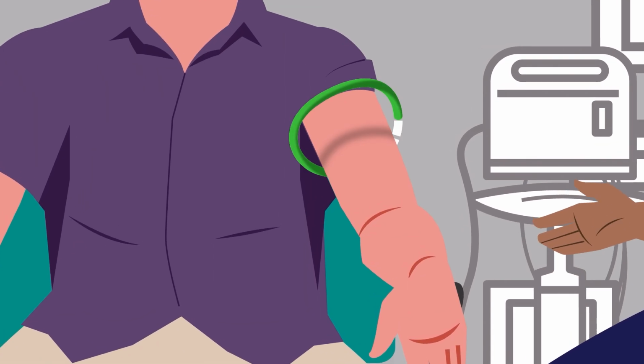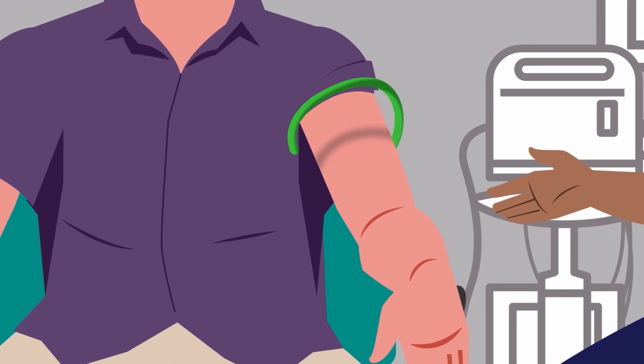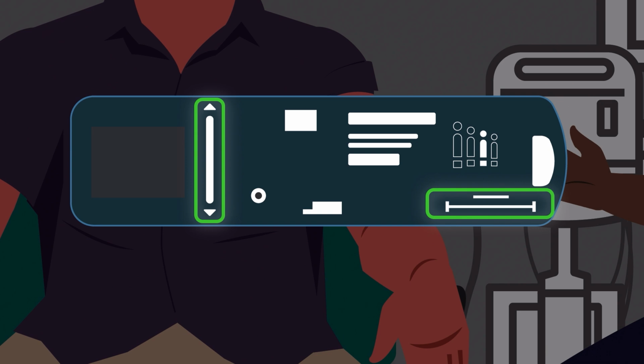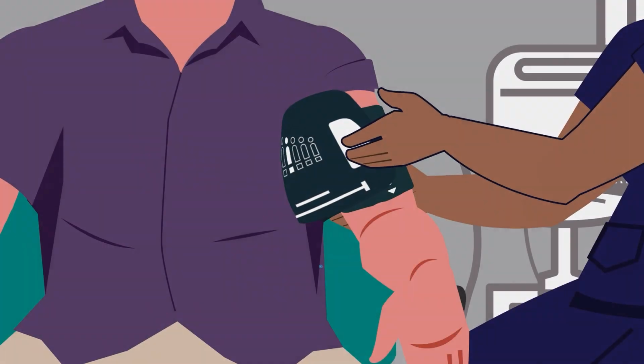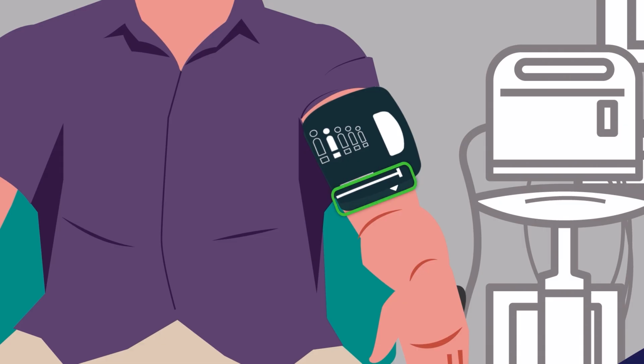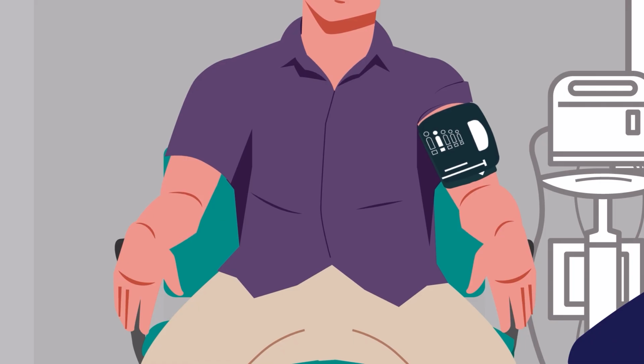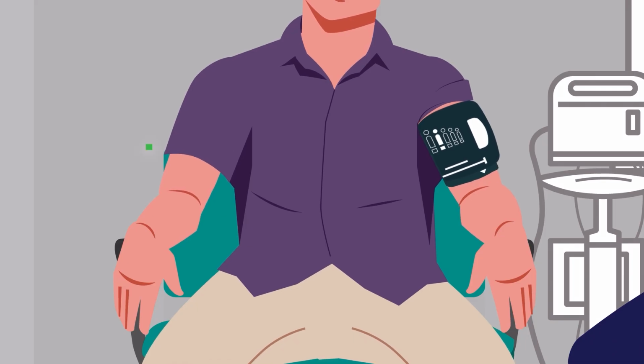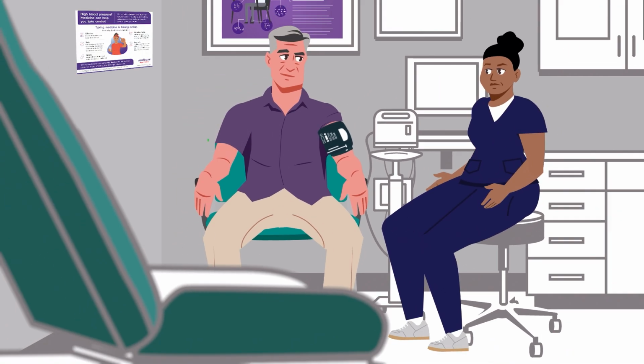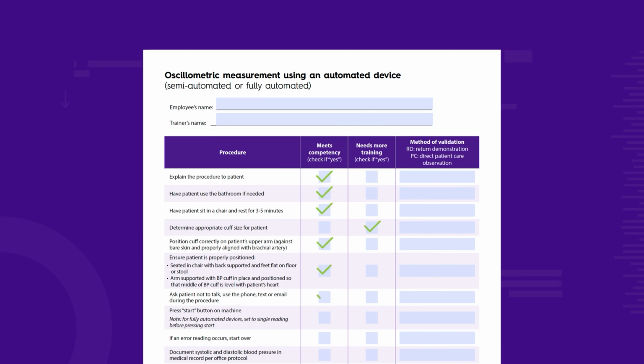Cuffs that are too small or too large can lead to inaccurate results. To select the best cuff size, measure the circumference of the mid-upper arm. Many cuffs have range and index lines that can help make sure the cuff size is right. When the cuff is wrapped around the patient's arm, it should be snug, and the index line should fall inside of the range line. Remember, always place cuffs on patients' bare upper arms and make sure their arms are supported so that the cuff is at heart level. There should be no talking or texting while their blood pressure is being taken. Everyone who performs blood pressure measurements should have regular training, including competency checks, every 6 to 12 months to maintain best practices for measuring blood pressure.